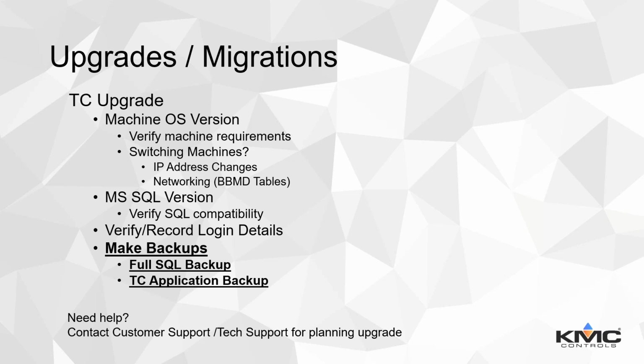However, you have two software solutions that are pulling that data and they're fighting for that information, so it does degrade performance. If you have multiple copies of software where it's not a client server application, where the WinControl is standalone and your TotalControl is client server, they're both making requests out on the line and fighting with each other. So it's okay, it works. It's just that long term you'll want to move away from that. But plan out your transition. It's all right if it takes time.